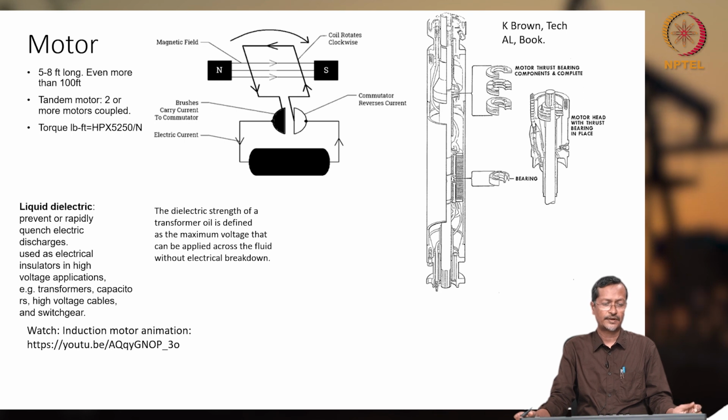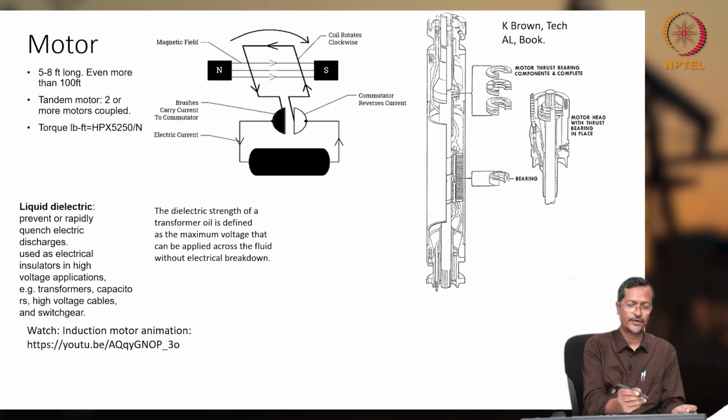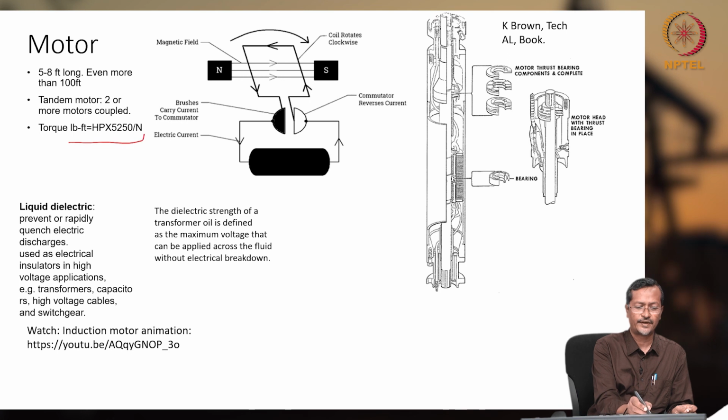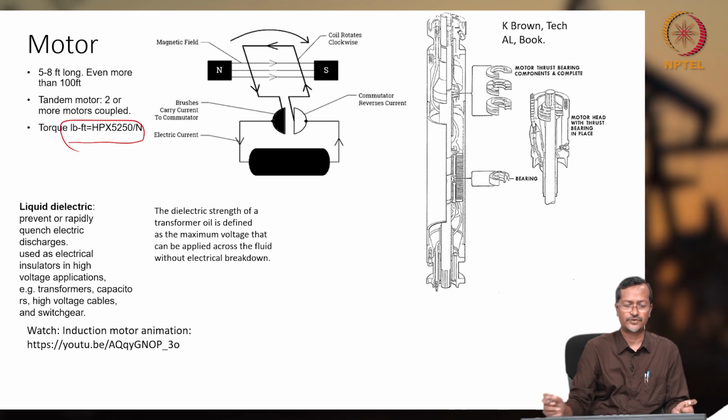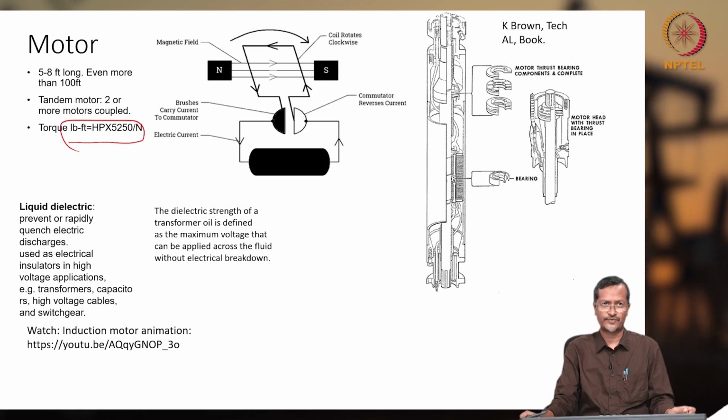And motor torque, if you calculate in pound-feet, is HP times 5250 divided by N. So this unique conversion factor, 5250, is there.